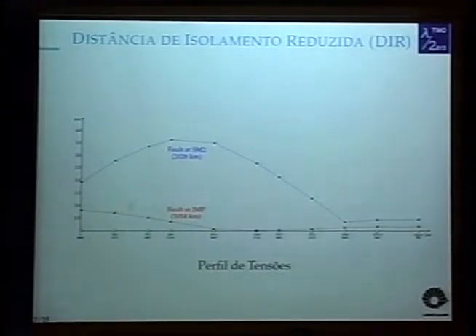To mitigate this, since large voltages and large currents happen throughout the line, including on the maneuver circuit breaker, it will not be possible to do a safe maneuver. So in order to remove this condition of almost quasi-resonance in the line, as mentioned before, we need to use a reduced insulation distance method that allowed for a discharge to be made in the Imperatriz substation, removing this condition from the system. Here we have the overvoltages for a fault happening in Imperatriz, which is approximately 1,000 kilometers away from the sending station, and we can see that it has never reached 1 per unit, 1 PU.